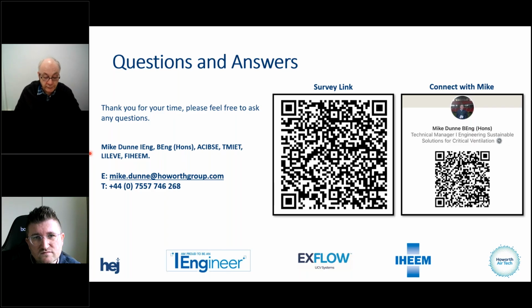There's one or two other questions. Somebody's asked, in terms of UCV systems, is there any use in taking static pressures adjacent to UCV recirculation fans when balancing a system? So you've got to be careful with UCV canopies. So there's inside the canopy, there's obviously a recirculation fan. The recirculation fan is in series with the AHU fan. So the AHU fan is pushing volume down the air handling unit, and then the UCV is snatching that volume and it's pushing it over the HEPA filters.